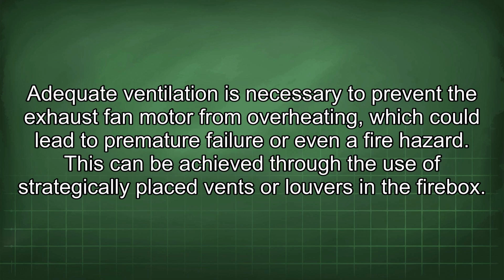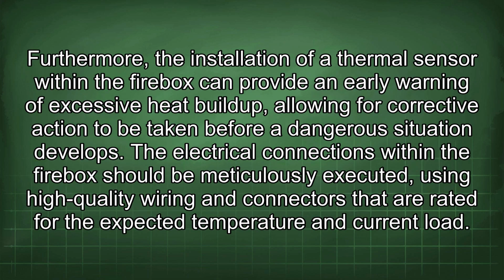Adequate ventilation is necessary to prevent the exhaust fan motor from overheating, which could lead to premature failure or even a fire hazard. This can be achieved through the use of strategically placed vents or louvers in the firebox. Furthermore, the installation of a thermal sensor within the firebox can provide an early warning of excessive heat buildup, allowing for corrective action to be taken before a dangerous situation develops.